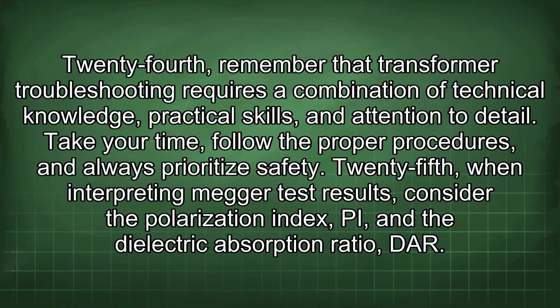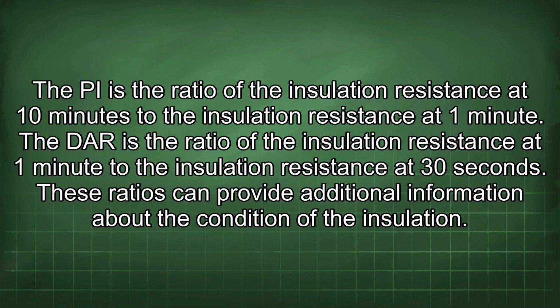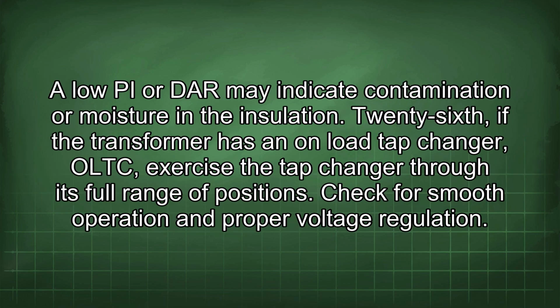25th, when interpreting megger test results, consider the polarization index (PI) and the dielectric absorption ratio (DAR). The PI is the ratio of the insulation resistance at 10 minutes to the insulation resistance at 1 minute. The DAR is the ratio of the insulation resistance at 1 minute to the insulation resistance at 30 seconds. These ratios can provide additional information about the condition of the insulation. A low PI or DAR may indicate contamination or moisture in the insulation.